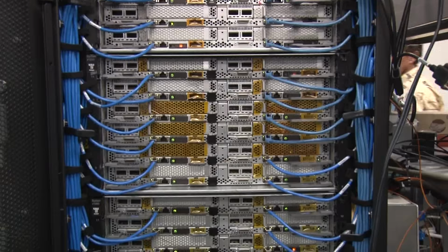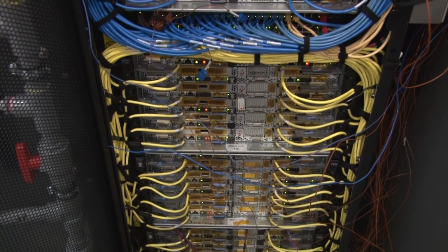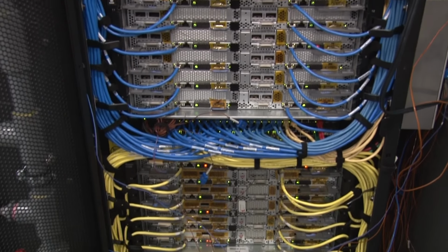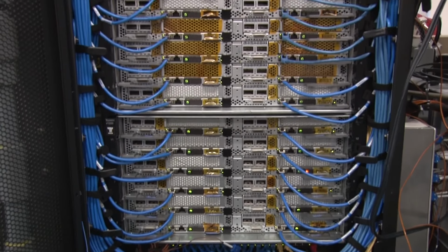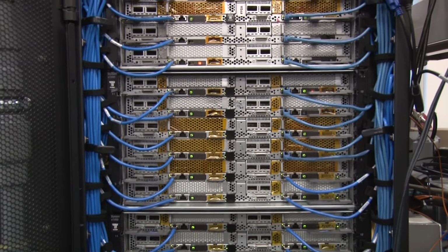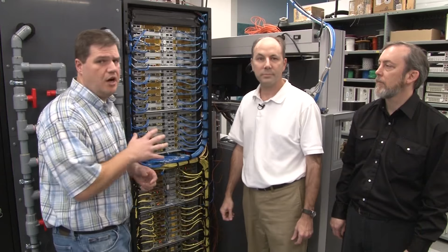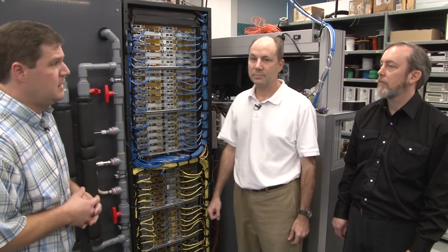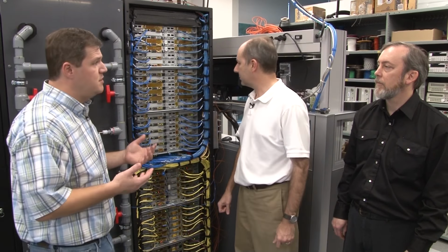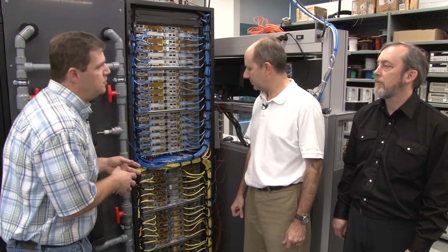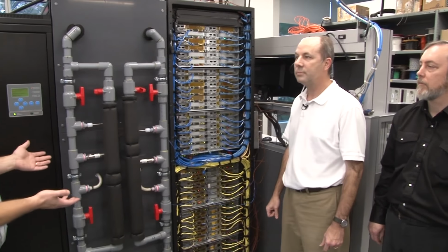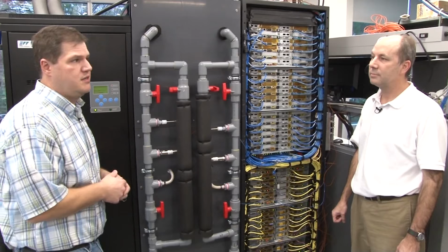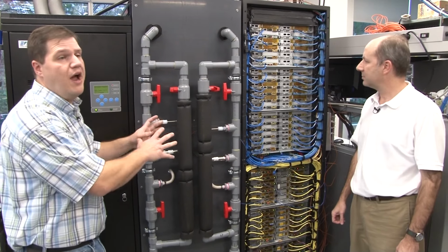Well, here's a 6 chassis rack that's got our full 6 racks worth of water-cooled nodes. Right now we've got Ethernet connected, and we're actually flowing and operating, so we're working under load right now. We're running an exerciser, M prime, so we've got about 28 kilowatts on the whole entire rack right now. And as you can see, we're in the lab environment, so we've got this connected to an instrumentation panel, which we use to make temperature and pressure measurements for the rack environment.